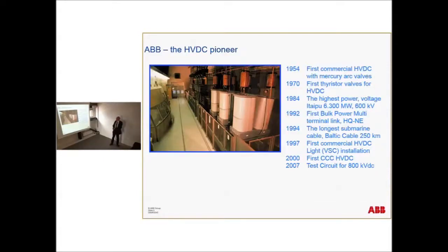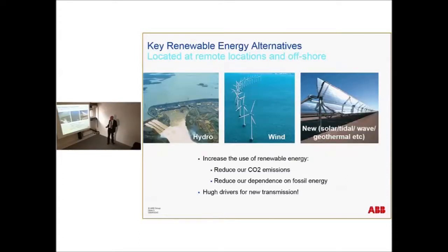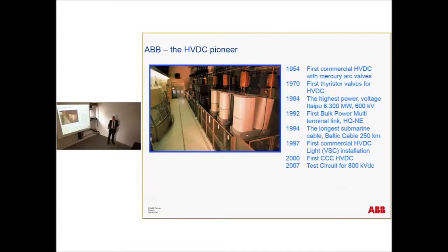We started already in 1954 with the first commercial HVDC. At that time it was with mercury valves. Then in 1970 came the thyristor. And if we go through this, we can see also we started with what we call the HVDC Light, which is the brand name of ABB's voltage source converters, in 1997. And in 2007, we had the first test circuit for 800 kV DC installed.